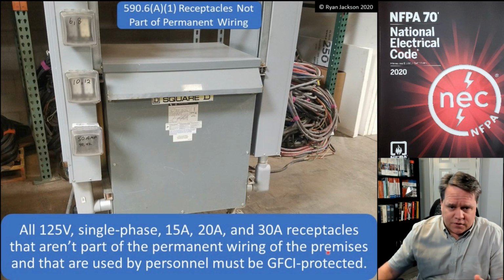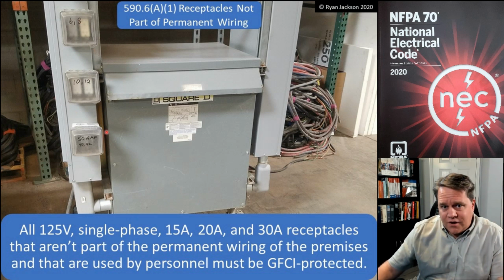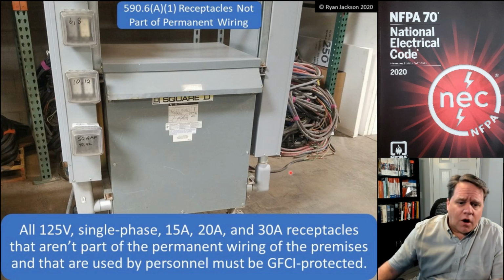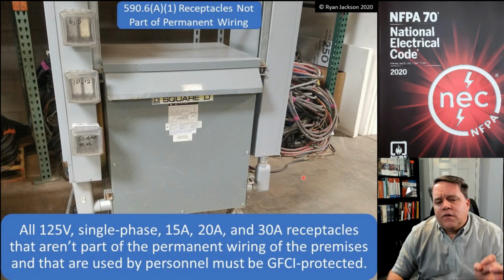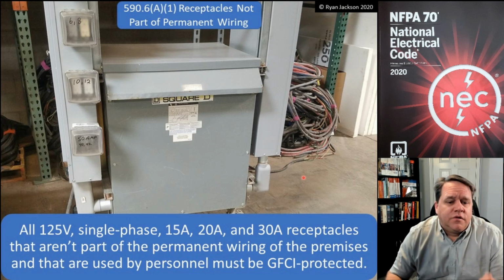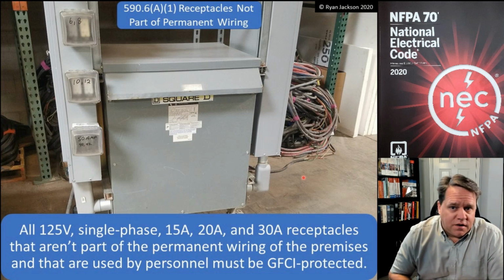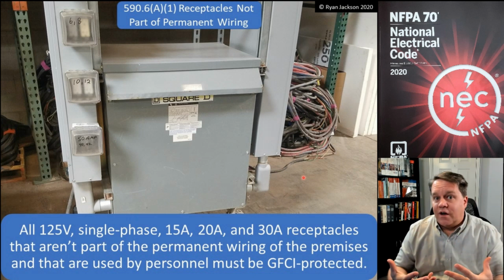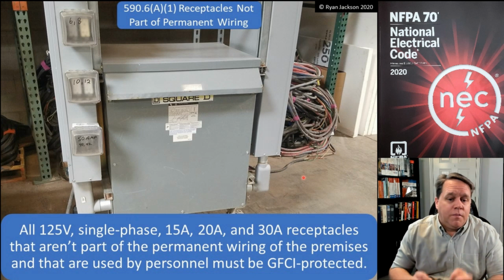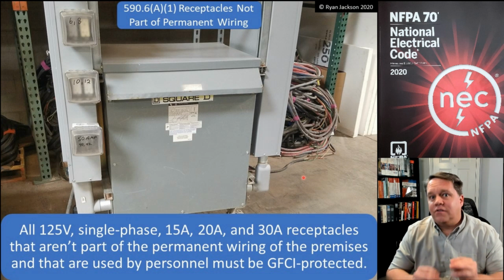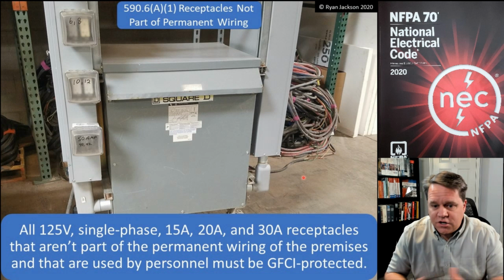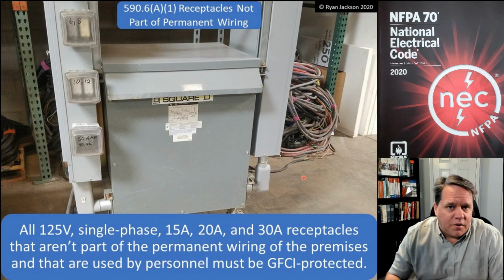So this receptacle here, I've got my 480 volt panel, my transformer, my 208 volt panel. I've got all of these receptacles on there. These are obviously not part of the permanent wiring. So all 125 volt, single phase, 15, 20, and 30 amp receptacles that are not part of the permanent wiring of the premises and that are used by personnel must be GFCI protected. Okay, so if it's temporary and those receptacles are being used by persons for activities like remodeling, repair, building, demolition, etc., they have to be GFCI protected.